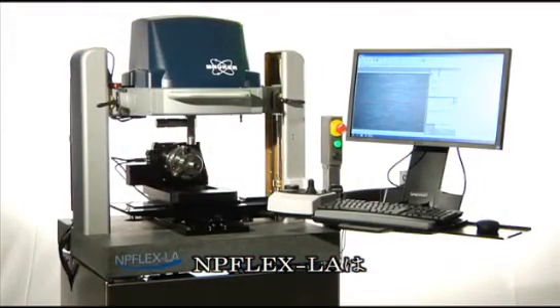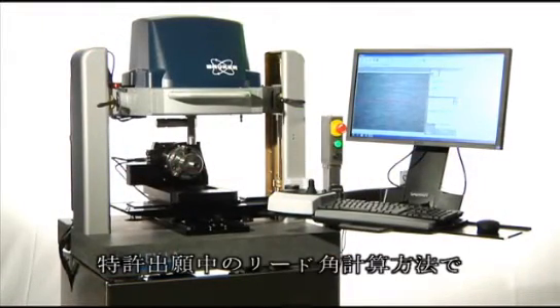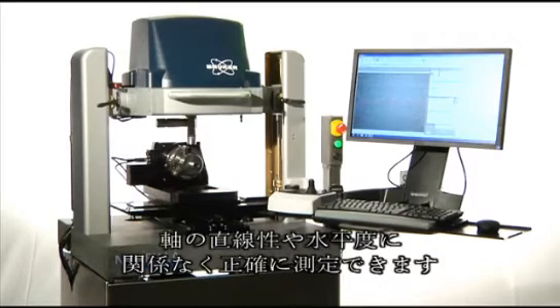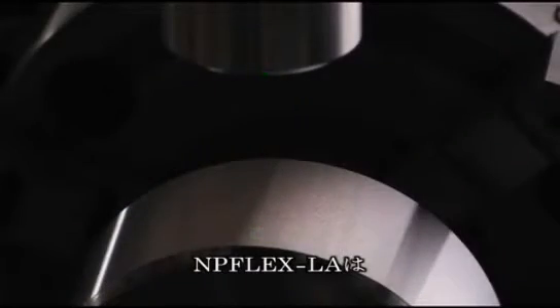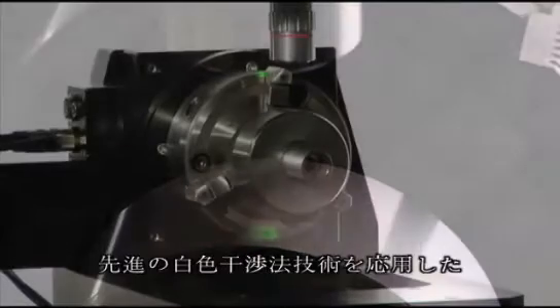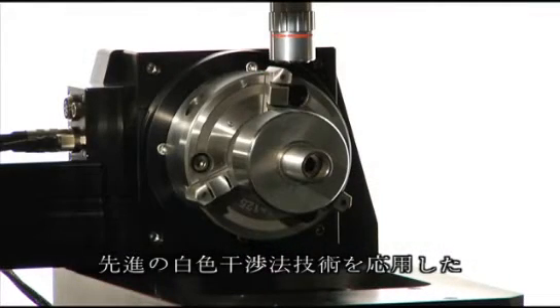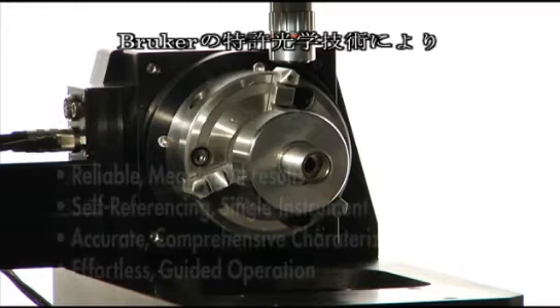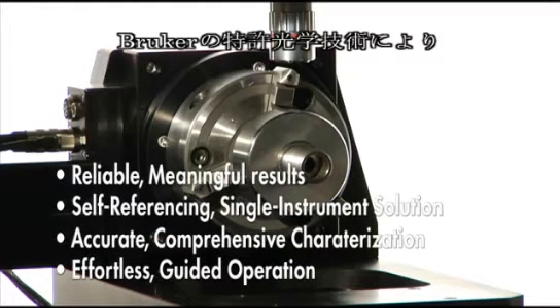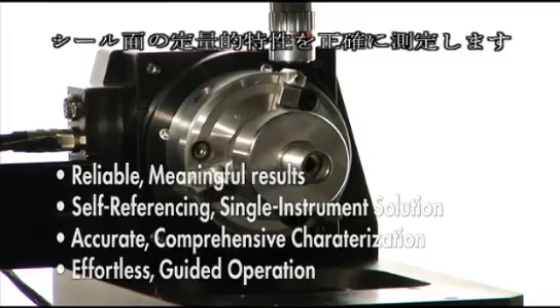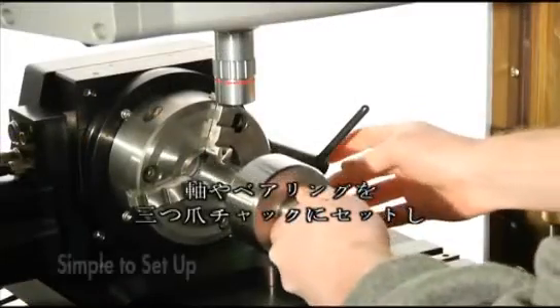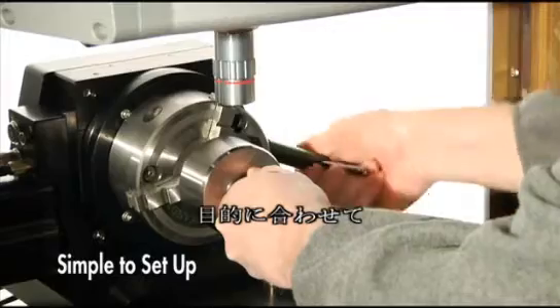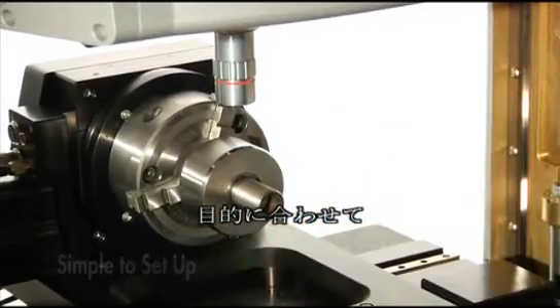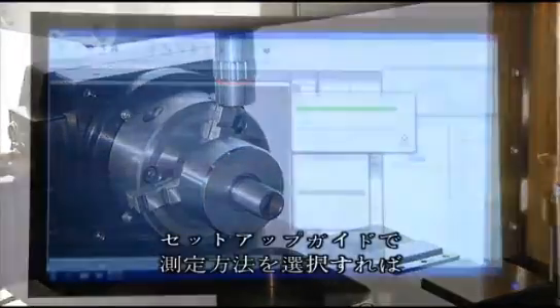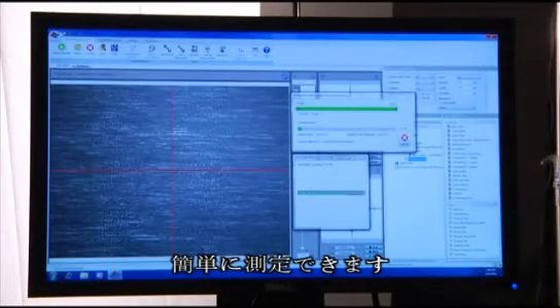With patent-pending algorithms and method for calculating lead angle, the NPFLEX-LA provides accurate measurements without concern for part alignment and level. Taking advantage of Bruker's patented optical technology, the NPFLEX-LA utilizes the latest advances in white light interferometry to provide meaningful, accurate, quantifiable characterization of the sealing surface. With an industrial 3-jaw chuck, the setup routine is as simple as mounting the shaft or bearing, focusing the objective, and selecting a measurement routine from the setup guide on the user interface.